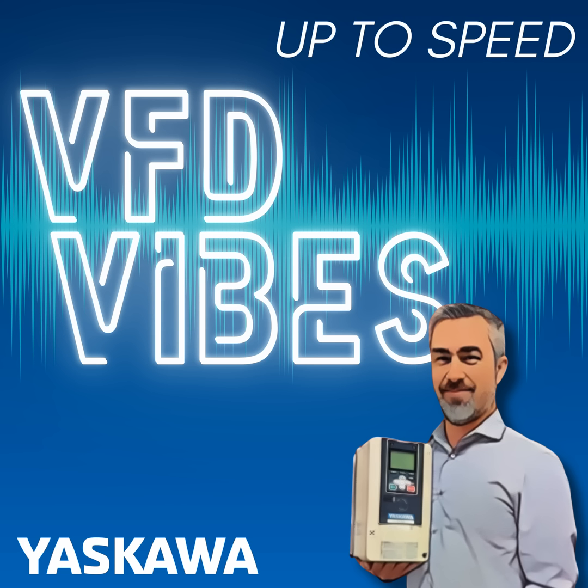These drives, some of them are available in unified packages, but traditionally have been available, as in the case of a multi-pulse drive, in a package where you have an inverter module, an active front-end module, the required filtering all in an electrical panel. But some manufacturers have taken the most popular sizes and integrated them into just one standard drive module that would look like any standard VFD, except it's a little larger physically.